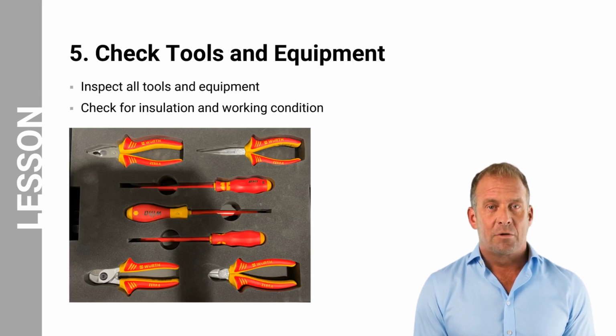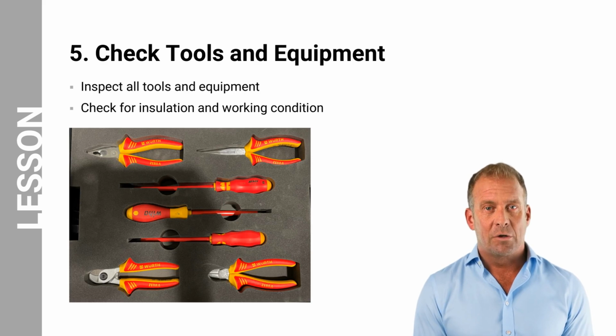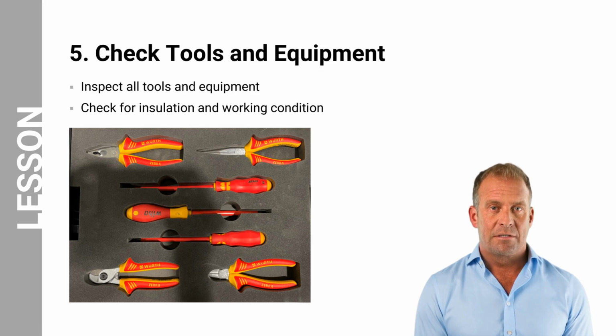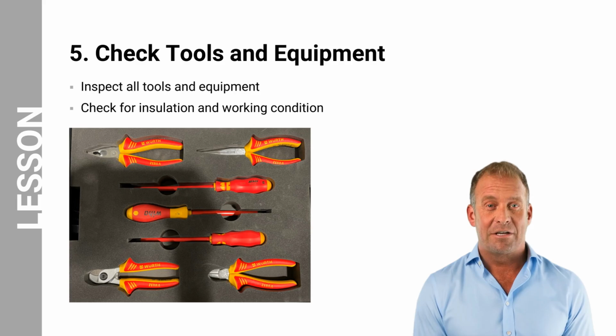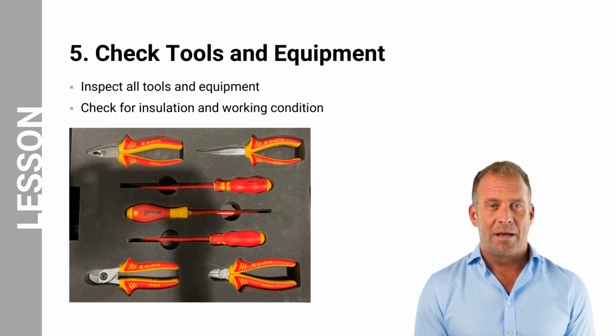Number 5, check tools and equipment. Before each use, thoroughly inspect all tools and equipment you intend to use. Ensure any specialized tools designed for electrical work on BEVs are properly insulated. Insulation helps prevent electrical conductivity and the risk of electrical shock. Look for any insulation damage or wear signs, such as exposed conductive parts. Some BEV brands and models may require specialized tools. These tools should be in excellent condition and used according to the manufacturer's recommendations.